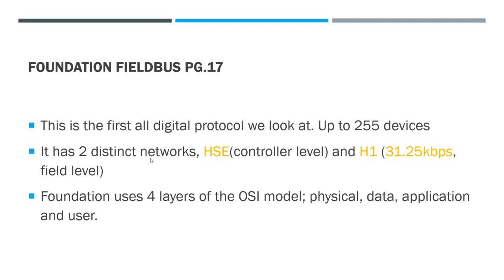We learned yesterday that it has two distinct networks: the high-speed Ethernet network, which was the controller level network, from the controller to the operator stations and administration stations, and also the H1 network, which was the fieldbus network out in the field. Data in the field network travels at 31.25 kilobits per second, which is much faster than the 1200 baud that we had in HART - so significantly faster. We went from a couple thousand - and I'm just generally rounding that number, it's not anywhere accurate - bits per second for HART to 31,000 bits per second for fieldbus protocol. So a significant improvement in data transfer speeds.